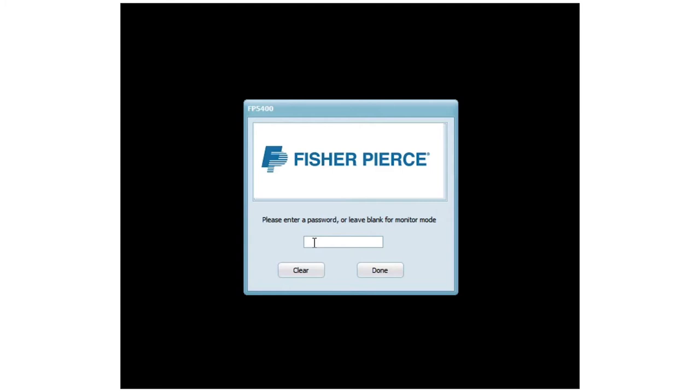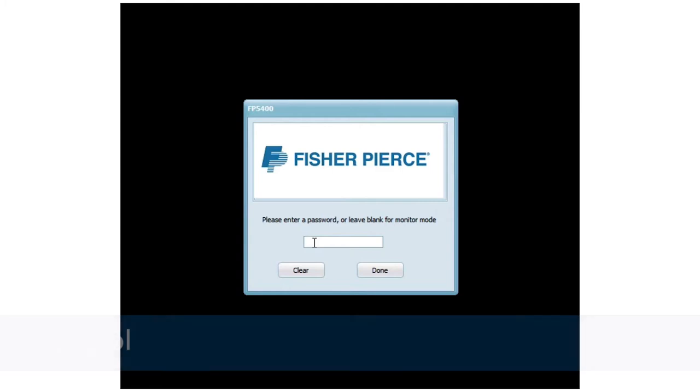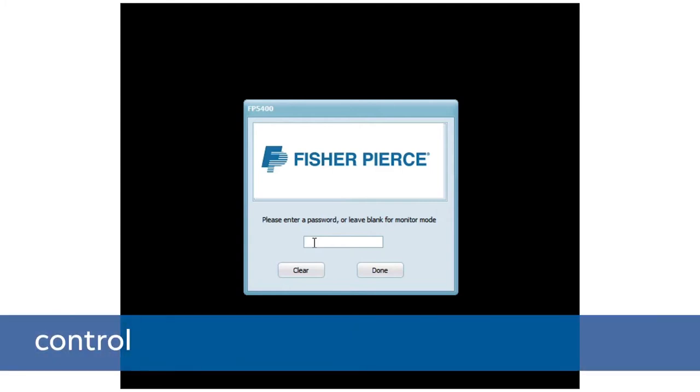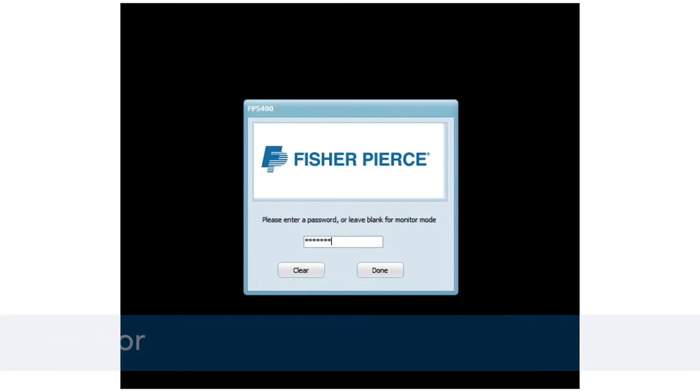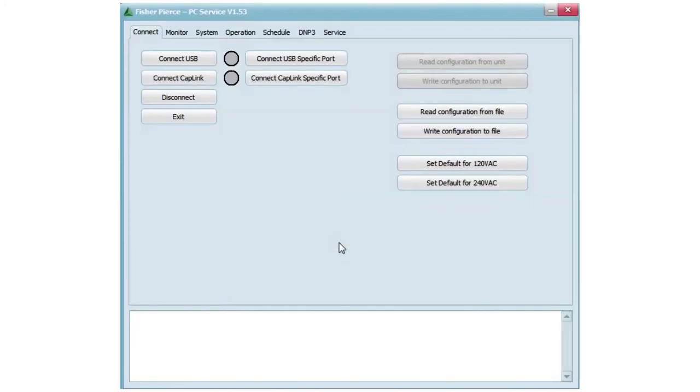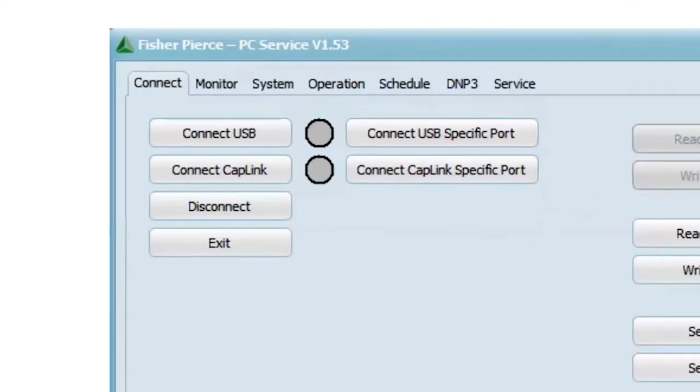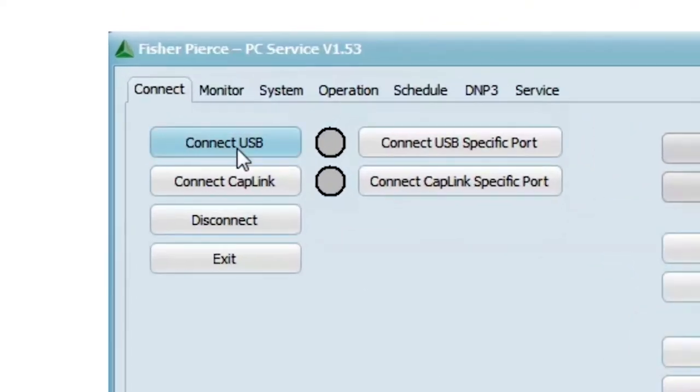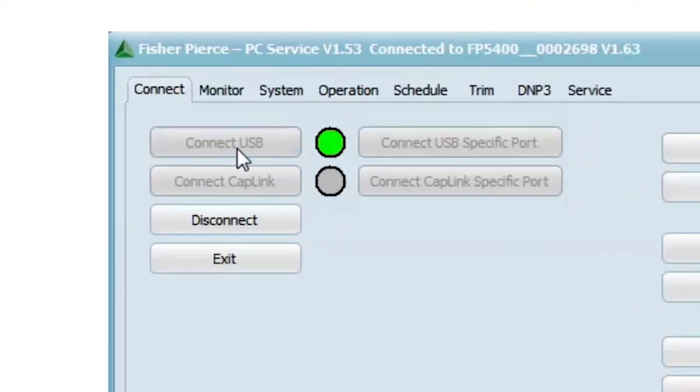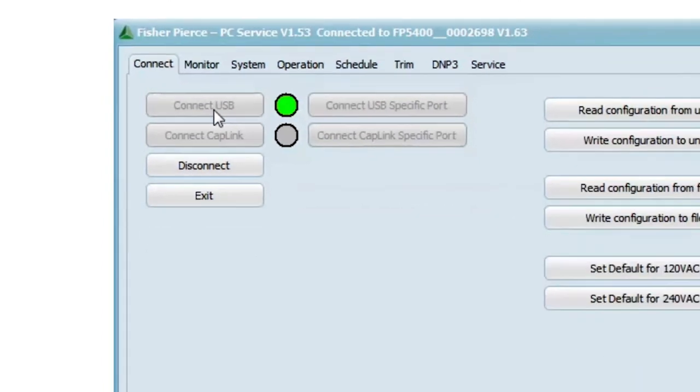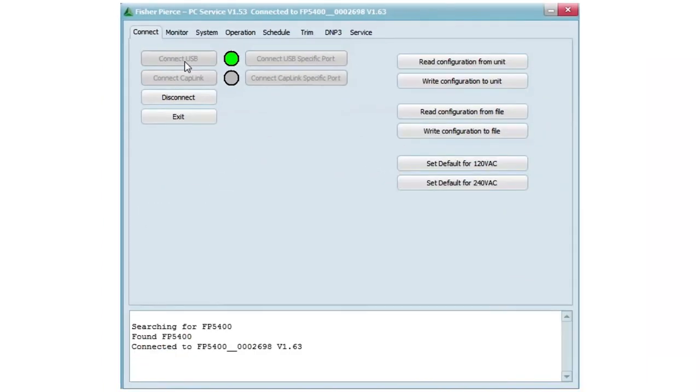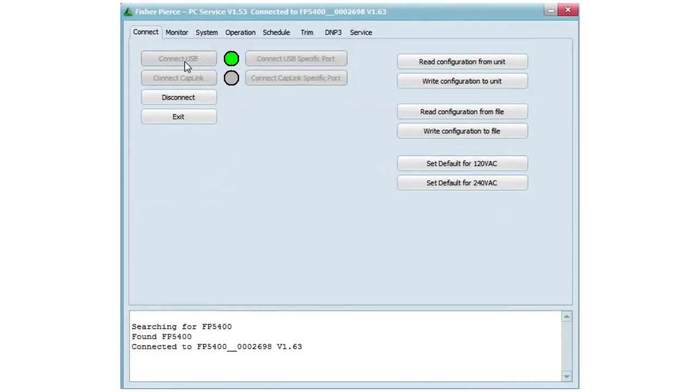When prompted for a password, the passcode is either 'control' or 'monitor' depending upon the function you want to perform. Once we get to the main screen, we will check the communications port for connection to the USB. You will notice the green light indicates communication is active and found the Fisher-Pierce controller. Now we can monitor or program the unit.